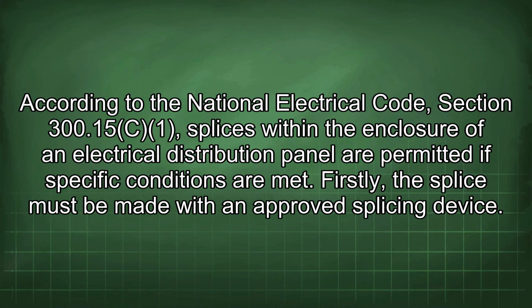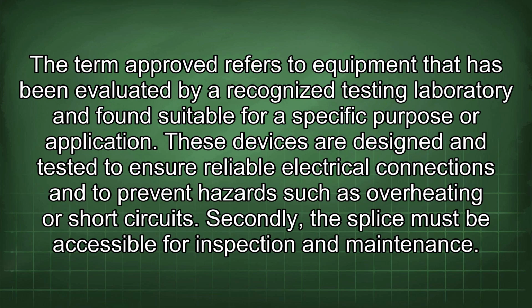According to the National Electrical Code, Section 300.15, splices within the enclosure of an electrical distribution panel are permitted if specific conditions are met. Firstly, the splice must be made with an approved splicing device. The term approved refers to equipment that has been evaluated by a recognized testing laboratory and found suitable for a specific purpose or application. These devices are designed and tested to ensure reliable electrical connections and to prevent hazards such as overheating or short circuits.